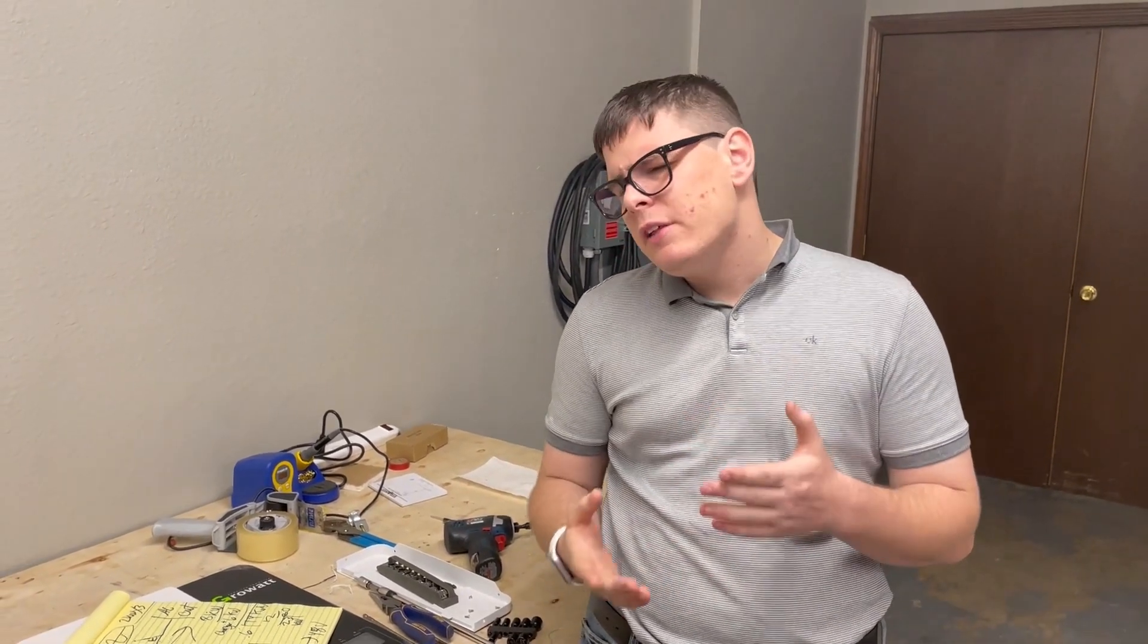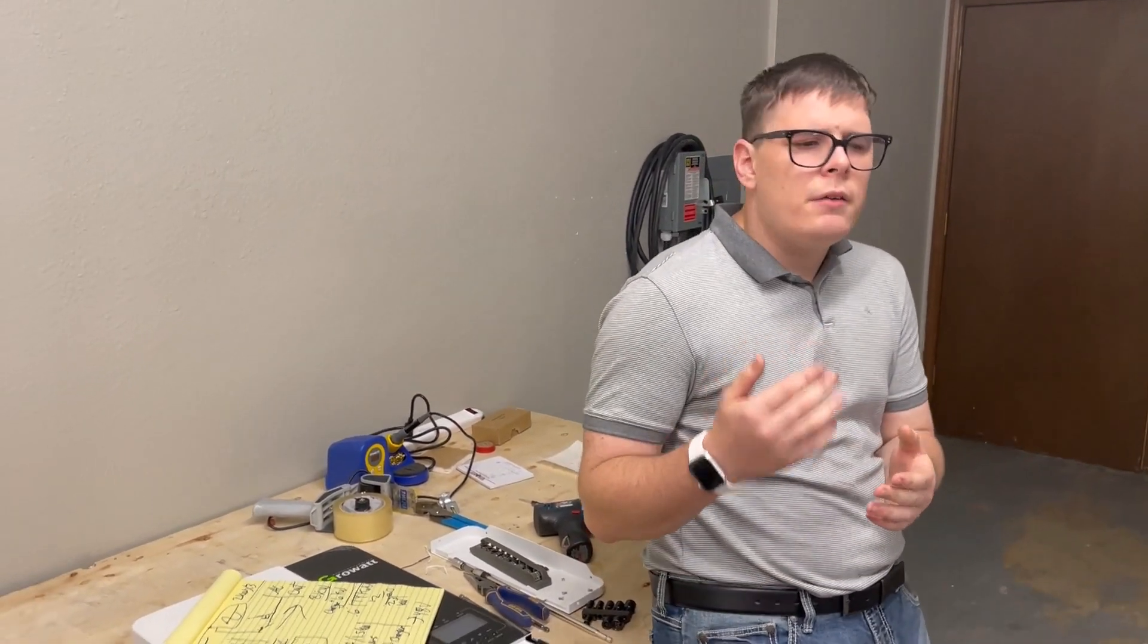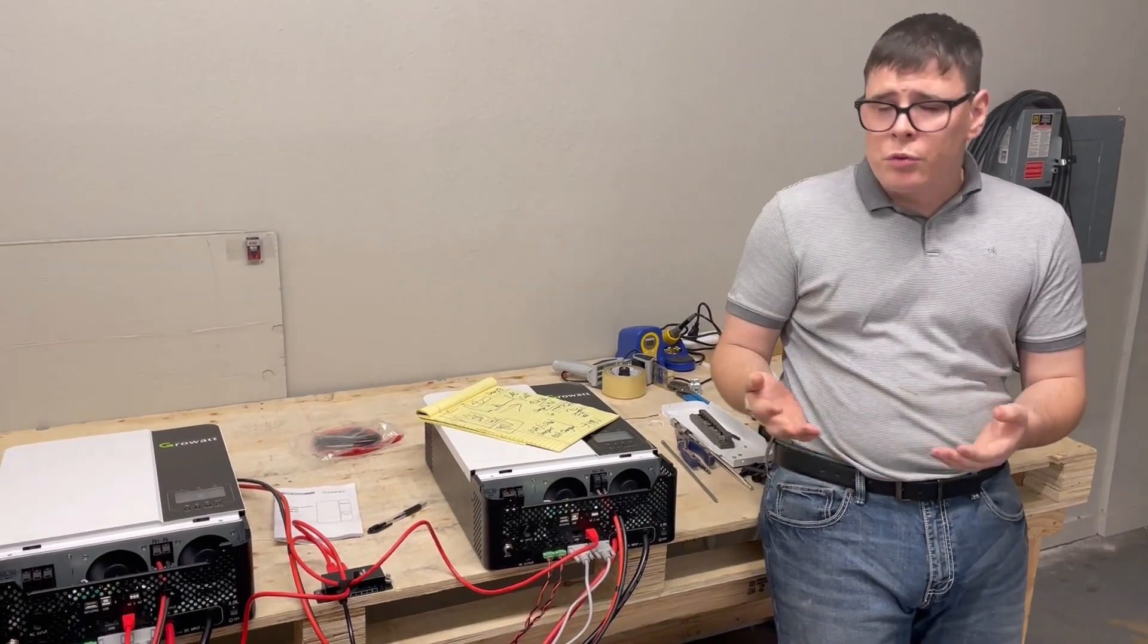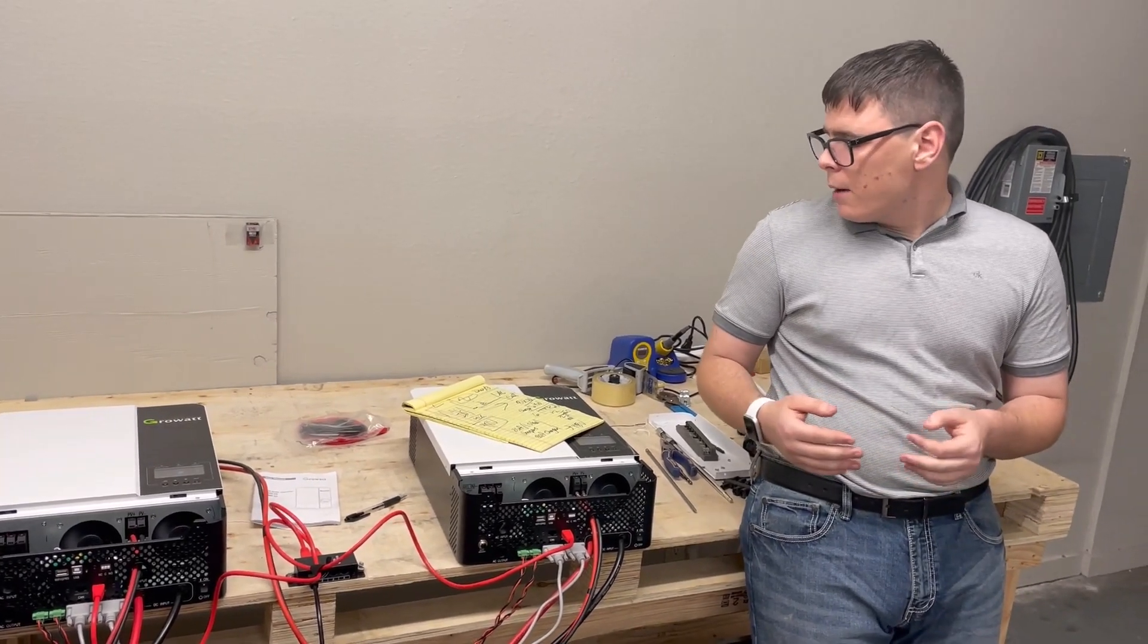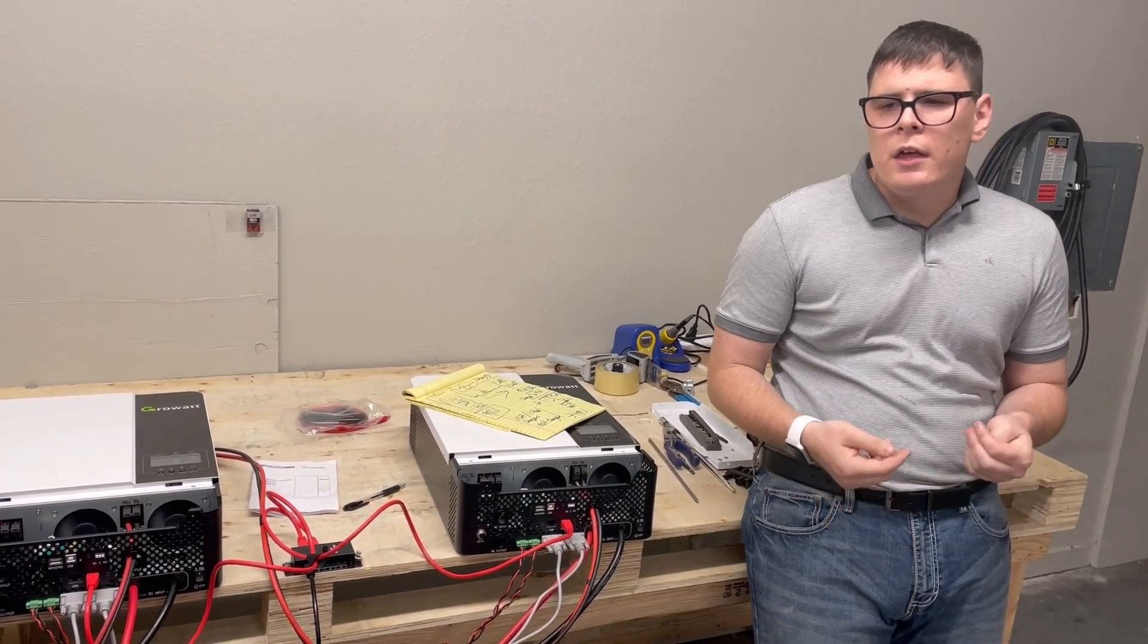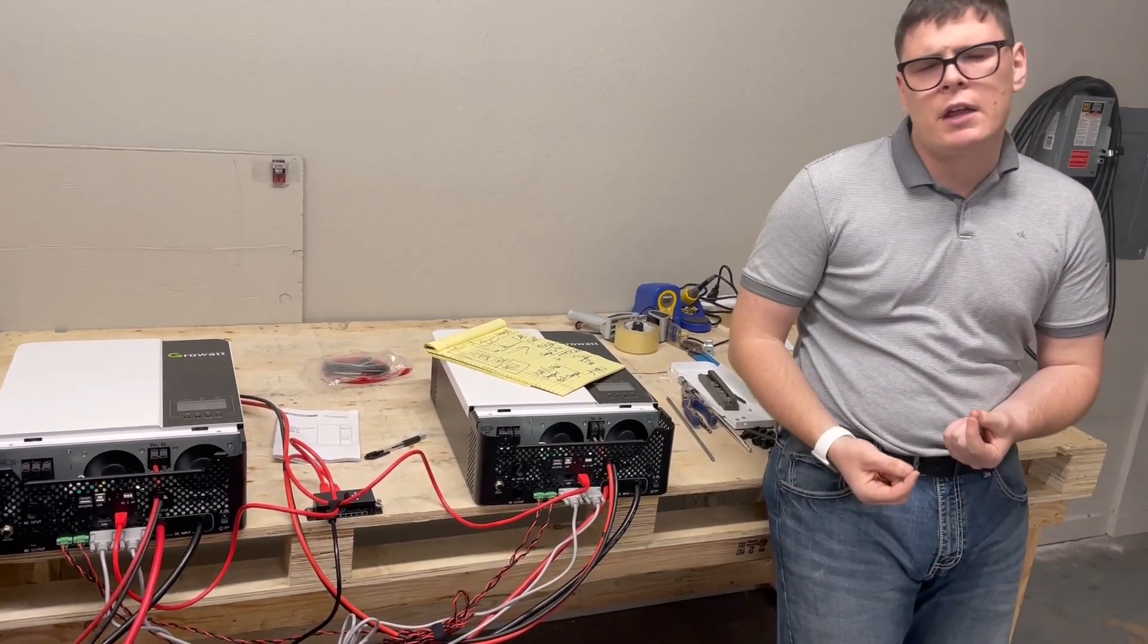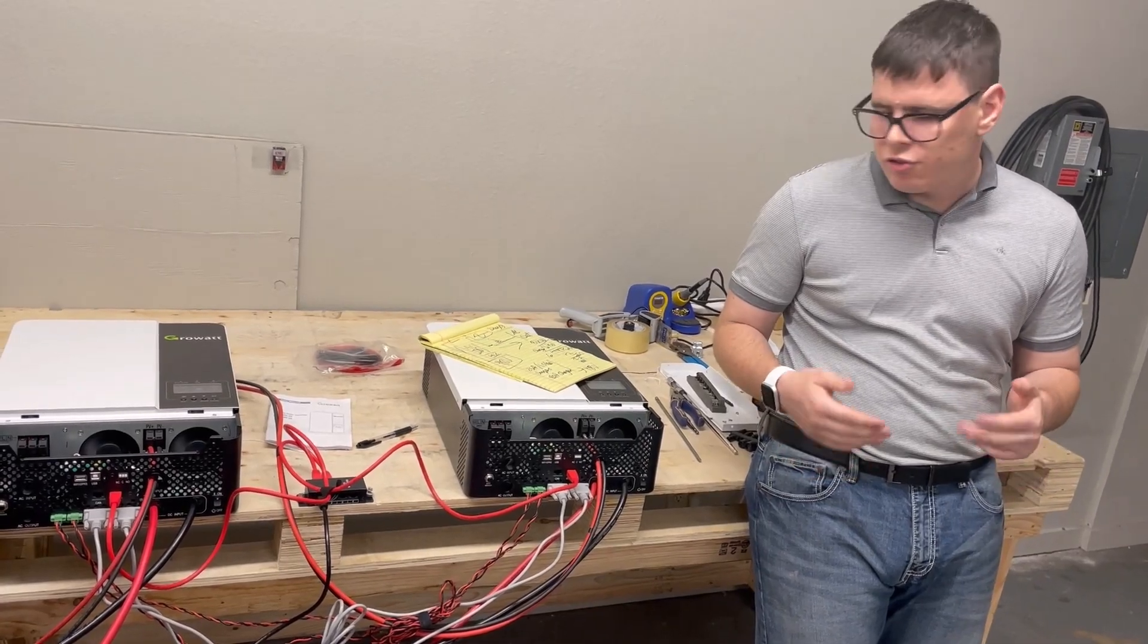That's really what we want to explain to most people about generators - it always comes up. The other thing to remember: a lot of people have these 5,000, 6,000 watt generators. You could say the 60% multiplier, but those cheaper ones tend to only go to 50%. So I'd much rather tell somebody to buy a couple of 1,500 watt chargers on their tractor supply generator than to try to backfeed one inverter, because they're just going to be tripping it, starving everything for power, and it's not going to end well.